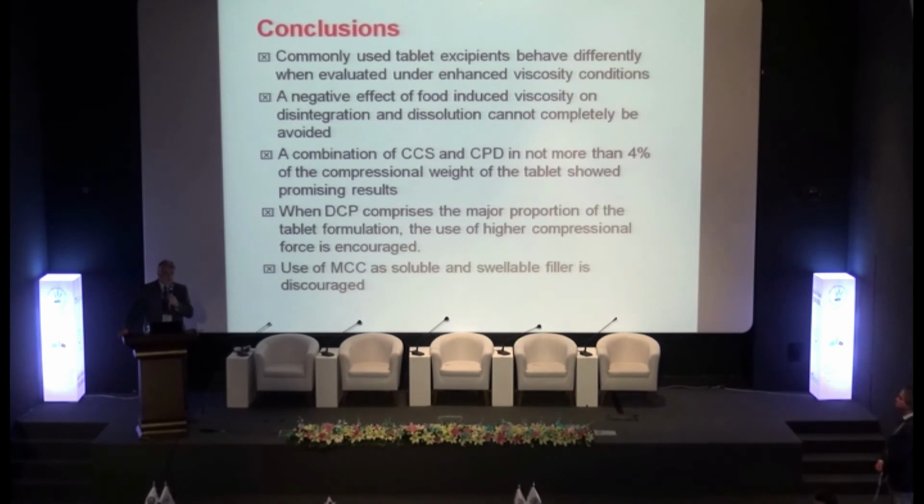I would say the difficulty sometimes with disintegration is that you need to identify and define a good endpoint. So you can say, okay, is it completely disintegrated when nothing is left on my mesh? Or is it disintegrated when it falls into granules already? We use high-speed cameras for that; we film the whole thing for each tablet, and we can then very clearly define the process for each product.